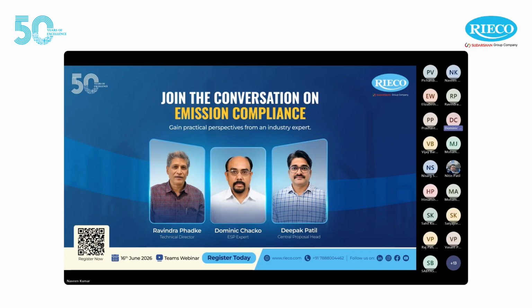Of course, ESPs have a limitation in collecting very low micron particles. That has been traditionally the problem with the ESPs. But of late, it's not uncommon for ESPs to have an emission as low as 10 to 15 milligrams per Nm cube also, with proper use of electrical technologies.